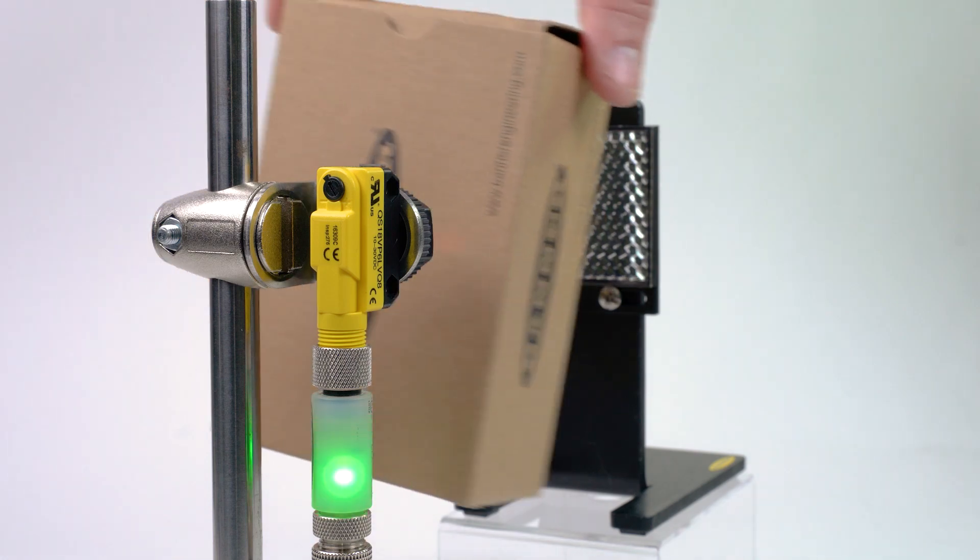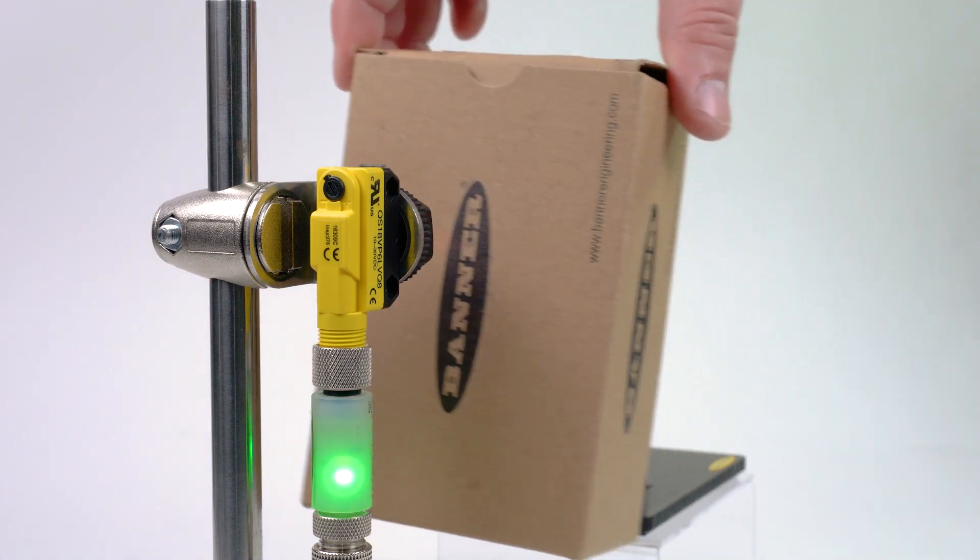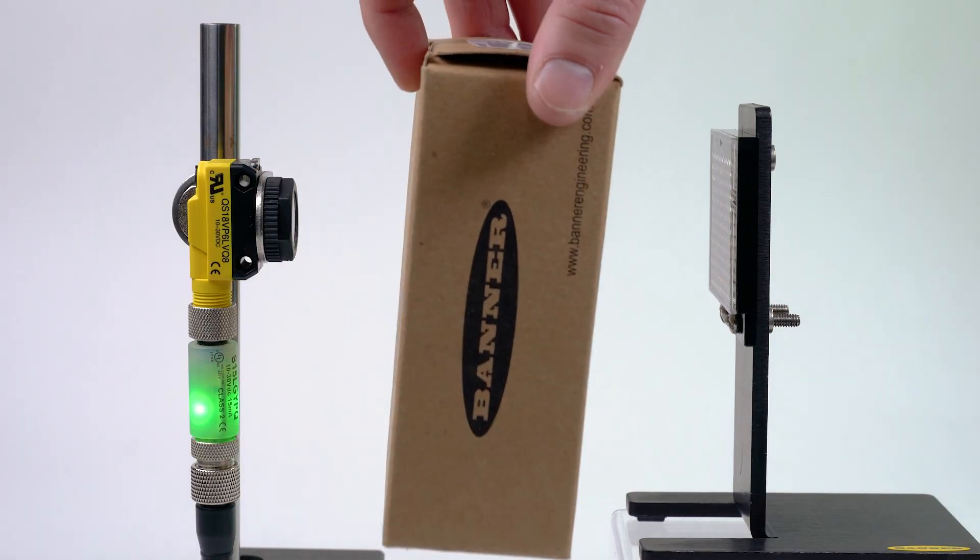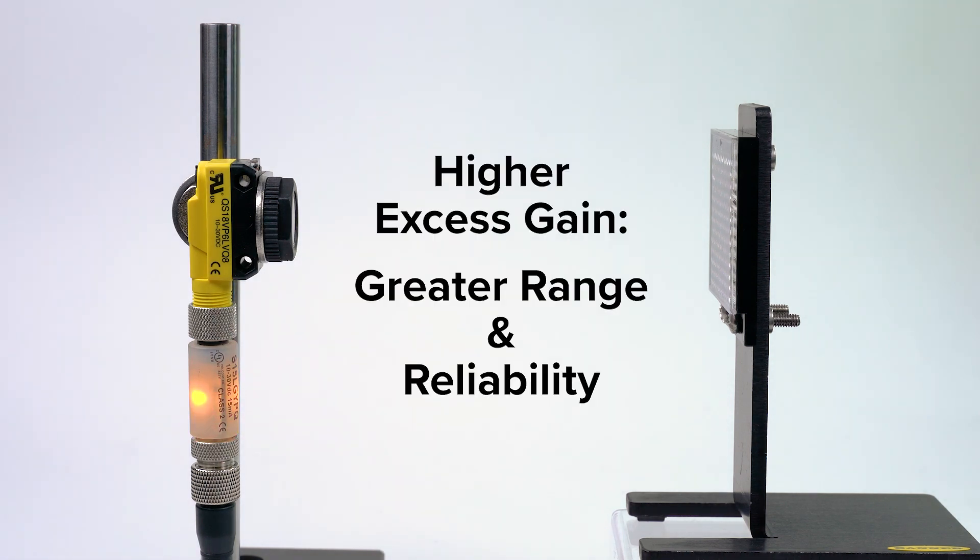A traditional retro reflective sensor is an excellent option for general detection applications of opaque objects without a reflective surface. It also provides the greatest amount of excess gain giving it a greater sensing range and reliability in dirtier environments.